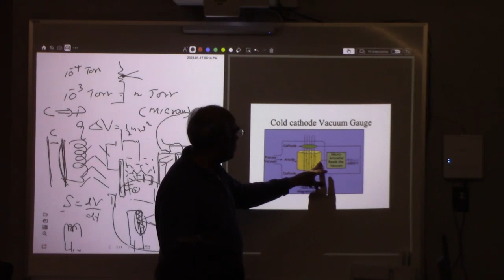Then there's something called the cold cathode gauge. In this one, there is no filament or anything. You apply a very large voltage between the cathode and the anode, so you emit electrons, and it's more like field emission, due to the voltage. Then you have a magnetic field. The magnetic field makes those helical paths, right? That's how they move, and in the process you can measure the current. That also depends on the pressure, right? Because we are applying voltage between anode and cathode, you just measure the current from that.